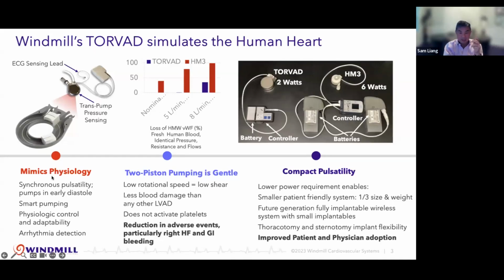Going to the middle of the slide, it's very gentle. It doesn't damage the blood. There's been extensive testing comparing the HeartMate 3 with the TORVAD, and it shows that as the pump speed of HeartMate 3 increases, it damages the von Willebrand factor. The final comments on the right-hand side are that because it's not on continuously, the TORVAD draws a lot less power, so it has much smaller system requirements in terms of its battery. It's about a third the size and weight of the current HeartMate 3 by Abbott, and it makes it a lot more patient-friendly. At the end, it's technology that we believe will improve outcomes through the reduction of adverse events and improve patient and physician adoption.